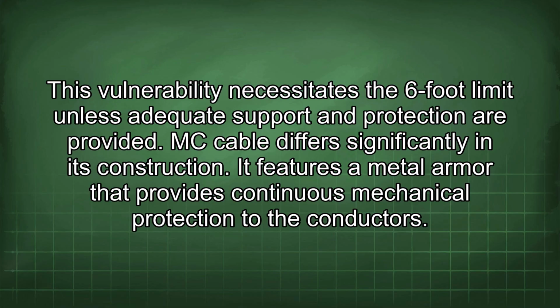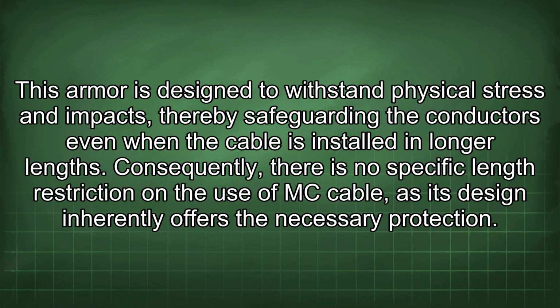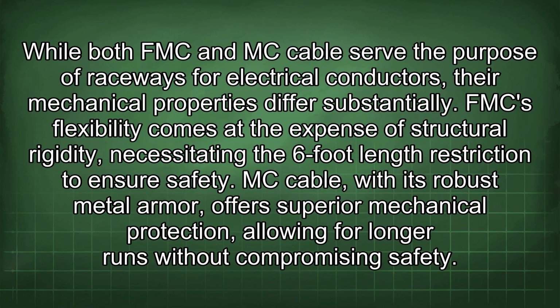MC cable differs significantly in its construction. It features a metal armor that provides continuous mechanical protection to the conductors. This armor is designed to withstand physical stress and impacts, thereby safeguarding the conductors even when the cable is installed in longer lengths. Consequently, there is no specific length restriction on the use of MC cable, as its design inherently offers the necessary protection.